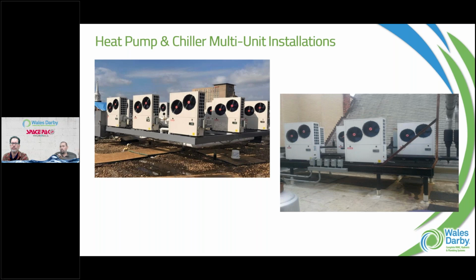You've got 5 banks of 5 tons. If you only need 5 tons and there aren't many people in the building, that's all we'll deliver to maintain the buffer tank. If we have more people and we're drawing temperature out of that buffer tank, more outdoor units will fire up. We don't need full capacity every time. By banking these units, it gives us a lot of different opportunities.